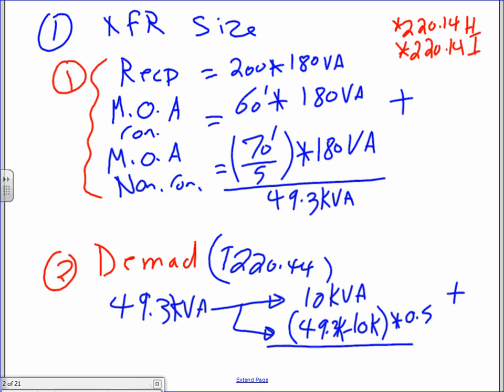You're going to add them up, and you'll end up with 29.6 kVA. And I'm not doing all the steps, guys. You're graduating now, right? So you do this math, multiply by 0.5, add the 10 to it, and you should come up with 29.6 kVA. Any comments, Karen? Any questions? So that's the demand load for the receptacles. You guys have done this in the load calculation. This is nothing new. That's what we did in the Excel sheet for the commercial project as well as for the industrial project.